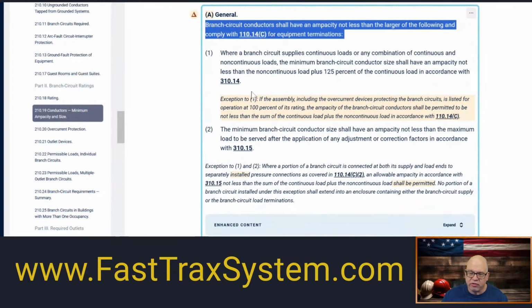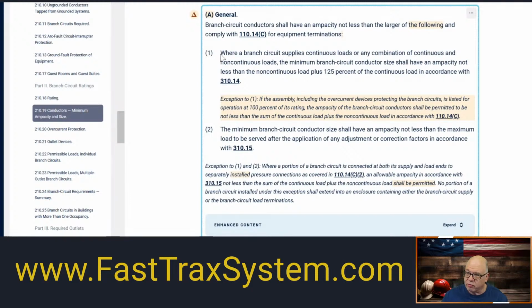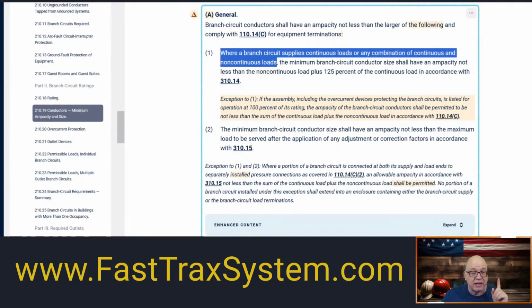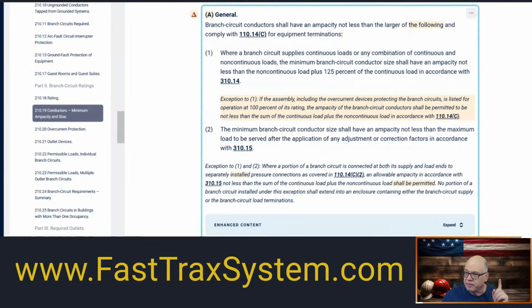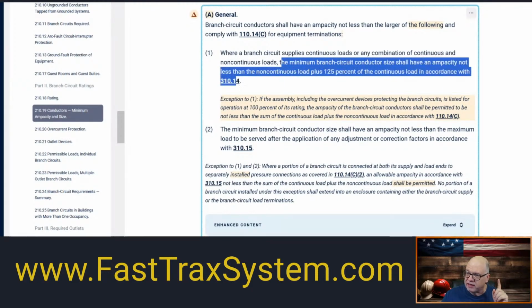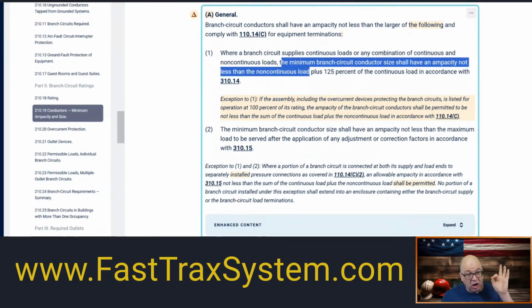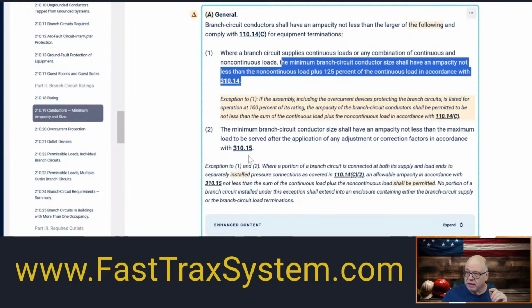Now, it says the larger of the two. Okay, so the branch circuit ampacity of a conductor cannot be less than the larger of the two. Well, the first one right here says where the branch circuit supplies continuous loads, and we had 10 amps of that, and any combination of continuous and non-continuous loads, that's what we have. It says the minimum branch circuit conductor size shall have an ampacity not less than the non-continuous load at 100%, plus 125% of the continuous load, okay? That's the first one. And it's the larger conductor that's yielded between either one of these.